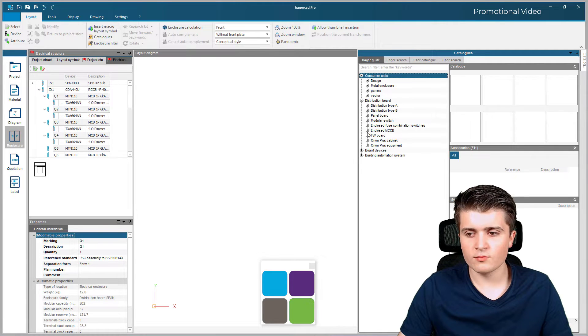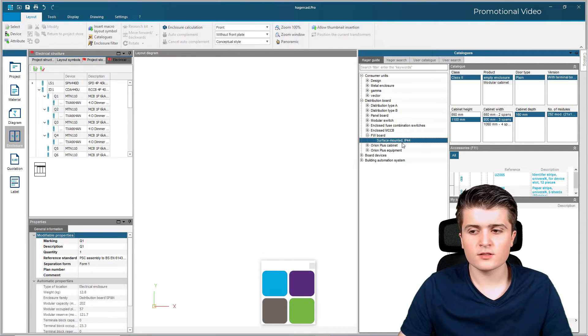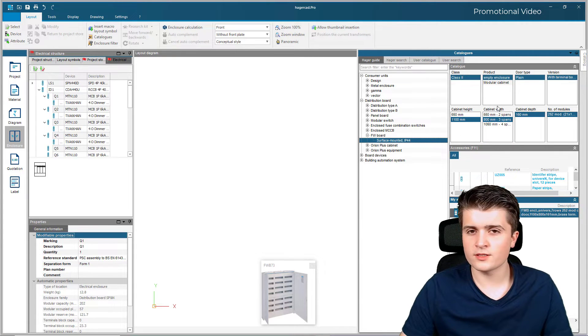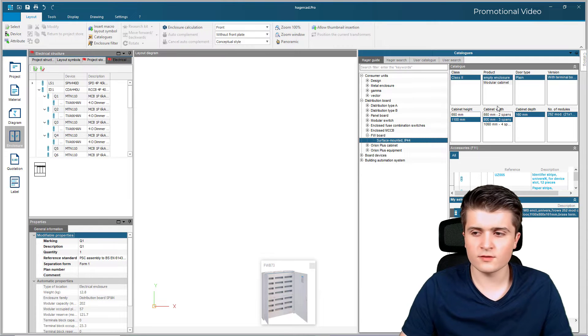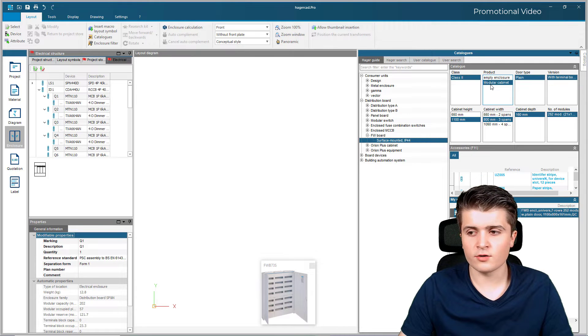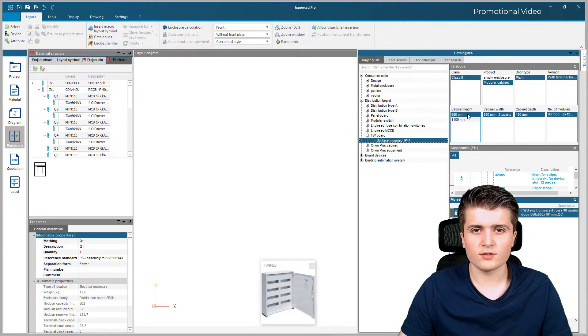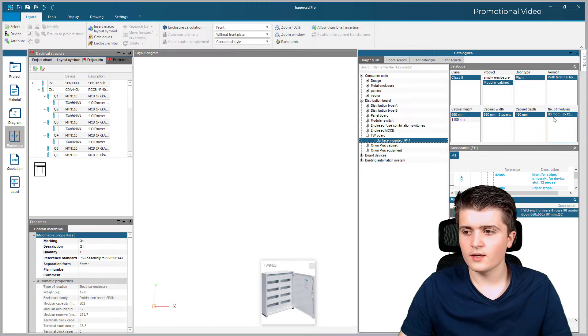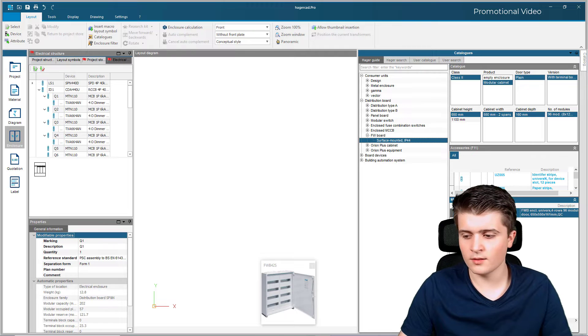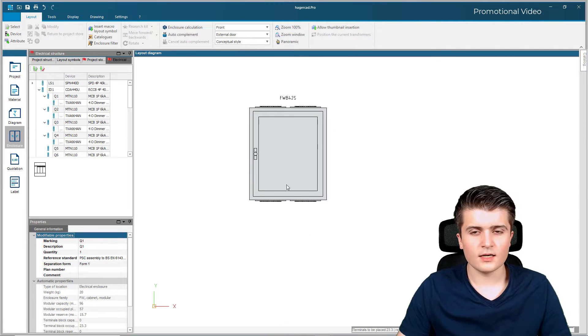Because I'm used to those enclosures, I want to use an enclosure like the ones in the German version. I can find this here within FW board surface mounted. You already know this window from circuit breakers or residual current devices — here we just set up the device, in this case the enclosure. I want a modular cabinet with the DIN rails already mounted, for example with the 650 millimeter height. Then I click on add and we have our enclosure.